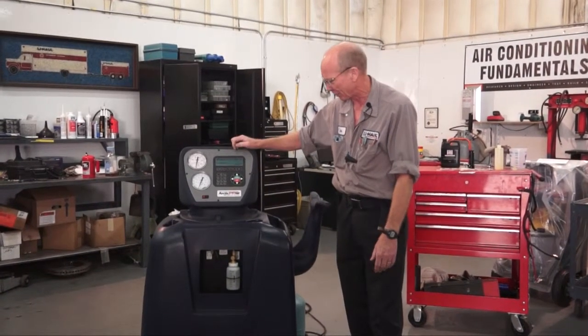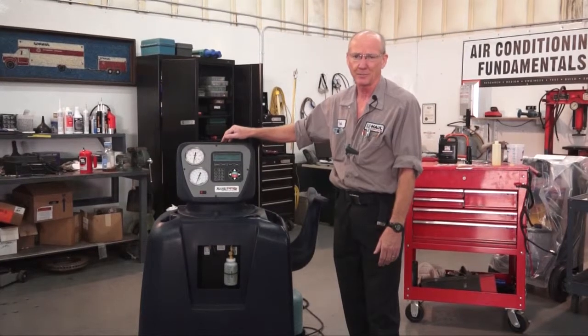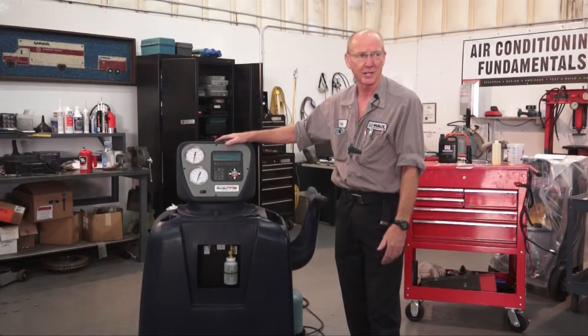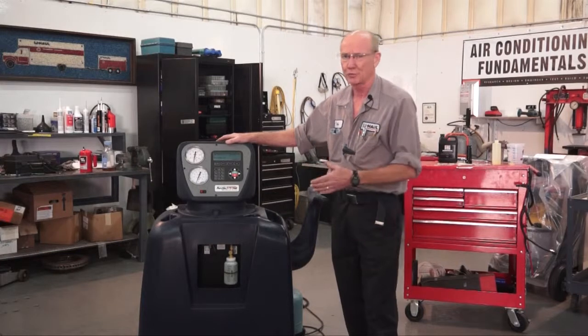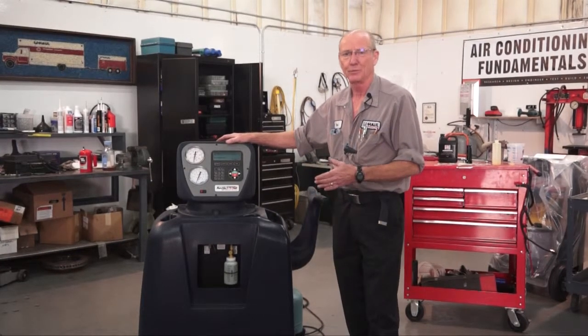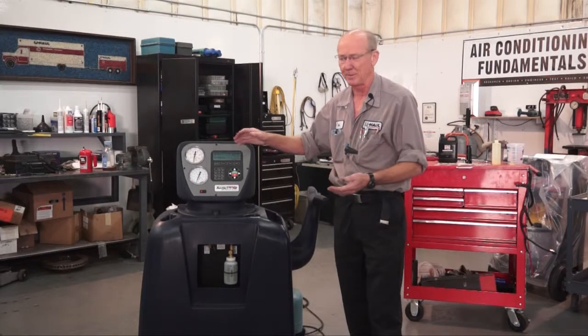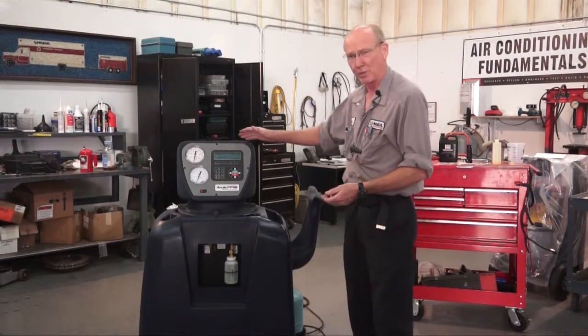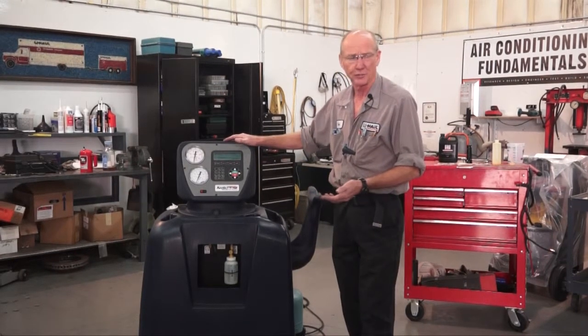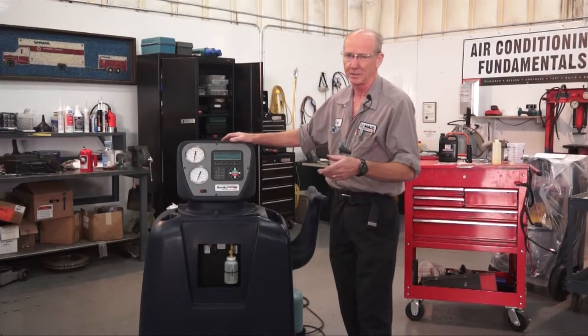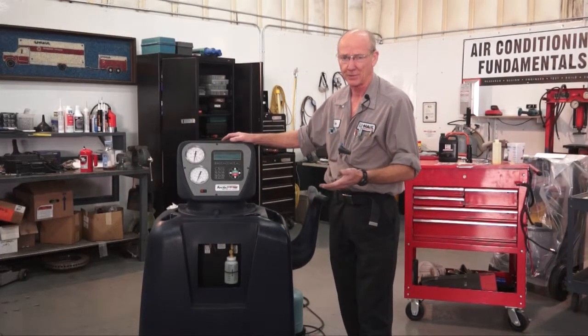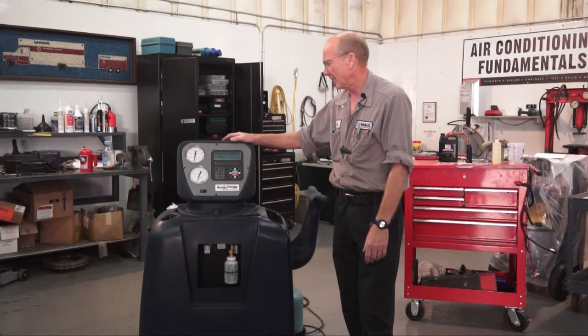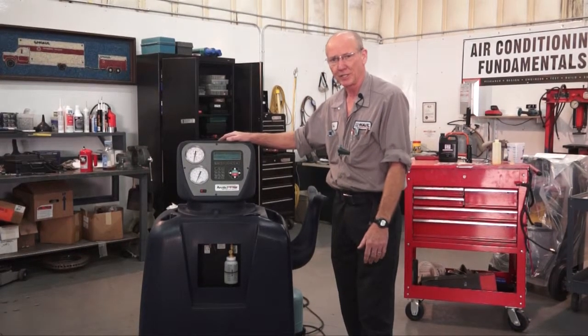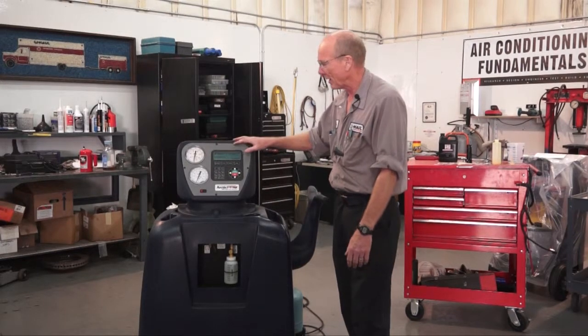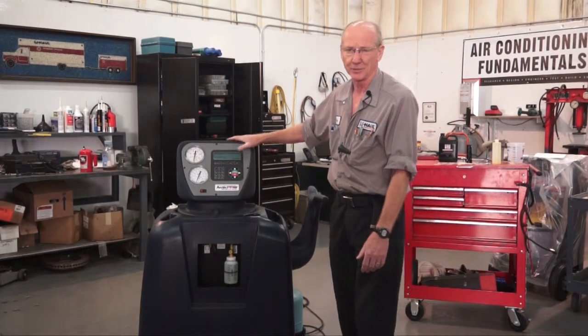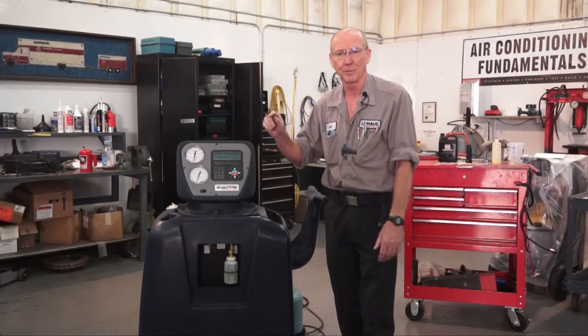You can get into that area of maintenance through the maintenance options on the machine. After 10 hours, the machine will prompt you. It won't shut the machine down. It'll prompt you to replace the vacuum pump oil. You may be in the middle of a service and it'll come up during that service, but continue your service. Don't hit yes, I'm going to replace that vacuum pump oil, because you may forget. Things get busy. Finish your service, then go back, get into the maintenance options on the machine, and hit yes, replace that vacuum pump oil.